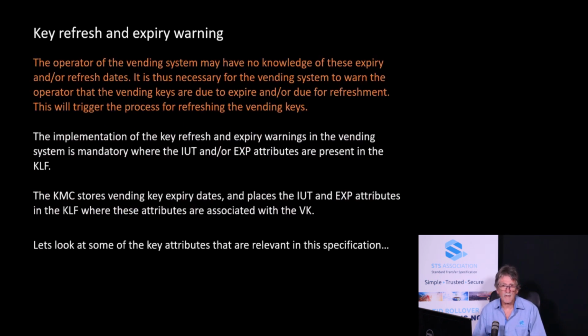So how does it work? The operator of the vending system may have no knowledge of these expiry or refresh dates. It is therefore necessary for the vending system to warn the operator that the vending key is about to expire or is due for refreshment. This will trigger the process for refreshing the vending keys. The implementation of key refresh and expiry warnings in the vending systems is mandatory where the IUT or EXP attributes are present in the keyload file.